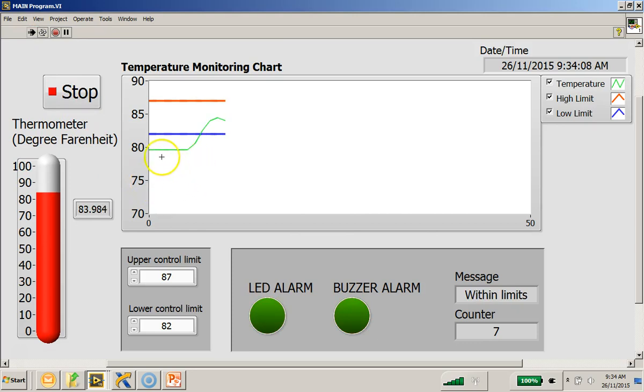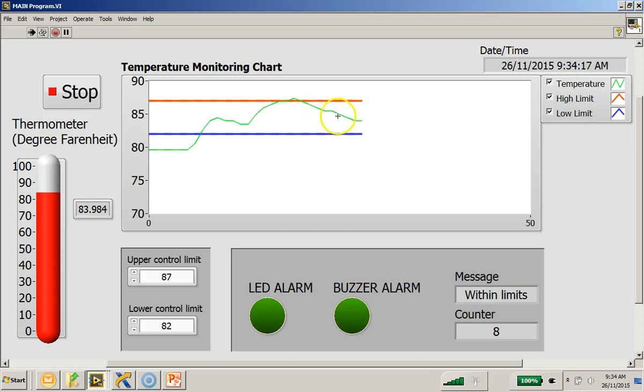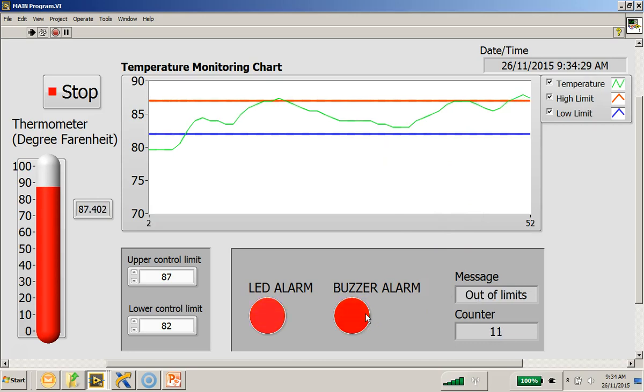What you can see is that this green color plot is the simulated temperature reading. And every time when this green reading is not within the upper limit and the lower limit, the alarm will be lit up. As you can see shortly, here we go.